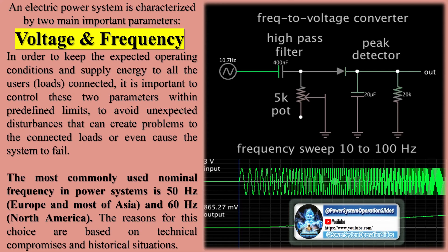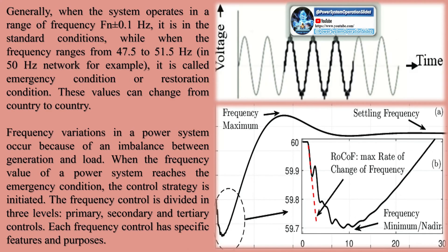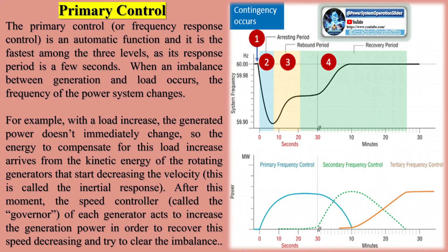An electric power system is characterized by two main important parameters: voltage and frequency. In order to keep the expected operating conditions and supply energy to all the user's loads connected, it is important to control these two parameters within predefined limits, to avoid unexpected disturbances that can create problems to the connected loads or even cause the system to fail. The most commonly used nominal frequency in power systems is 50 Hz in Europe and most of Asia, and 60 Hz in North America. Generally, when the system operates in a range of frequency plus or minus 0.1 Hz, it is in standard conditions, while when the frequency ranges from 47.5 to 51.5 Hz in a 50 Hz network, it is called emergency condition or restoration condition.